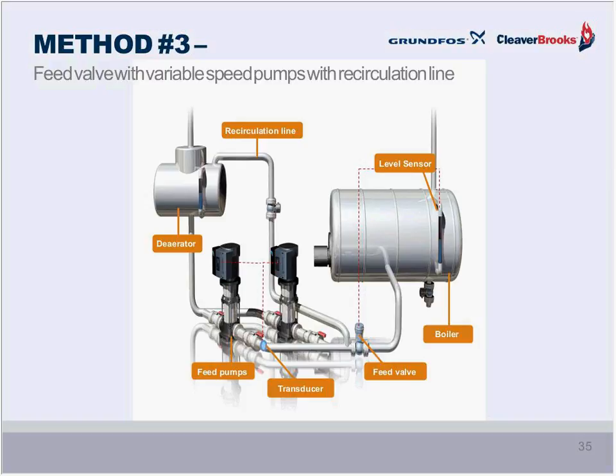Often this pump is controlled in a constant pressure mode. So as the water level sensor on the boiler indicates this raising and lowering of water in the boiler, the sensor sends that 4 to 20 milliamp signal that Steve mentioned to the feed valve, and there are some preset parameters. The feed valve modulates towards a more open or more closed position, depending on that need for flow.